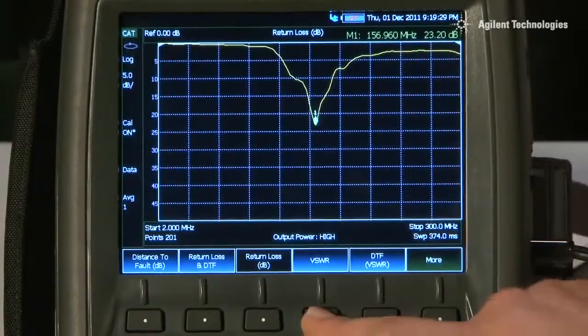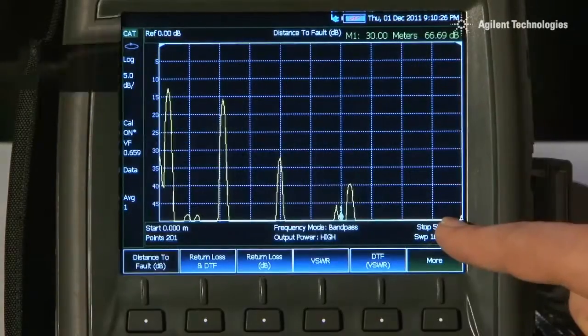It measures return loss, VSWR, cable loss and distance to fault and we can even make many of these measurements simultaneously.